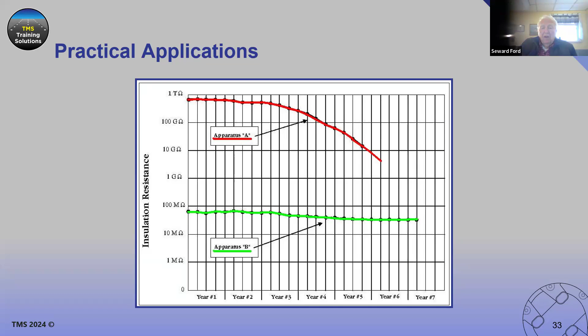Moving on, part of this is trend analysis as well. If you look strictly at the absolute values, apparatus A has a better value than apparatus B. But if you look at the curves with a downward trend of apparatus A, even though it has an initial higher absolute value, it's probably going to fail first. So you'd want to spend more attention figuring out what's wrong with apparatus A than apparatus B by looking at the trends. And that's the reason every time we measure our systems, we keep a record so we can look at those trends. I think that's the last slide we have.